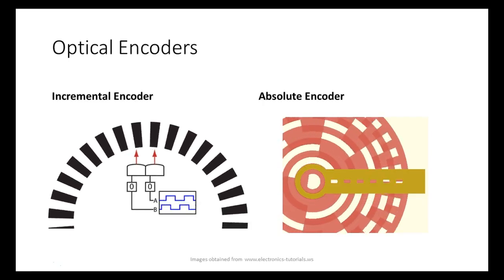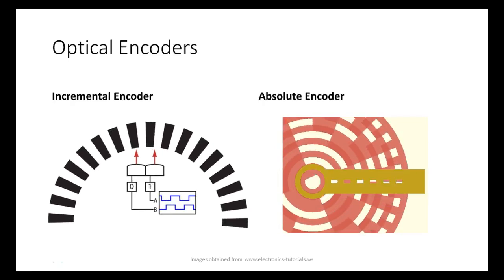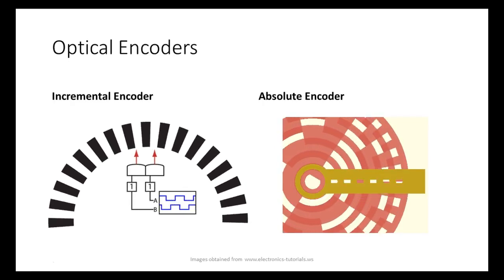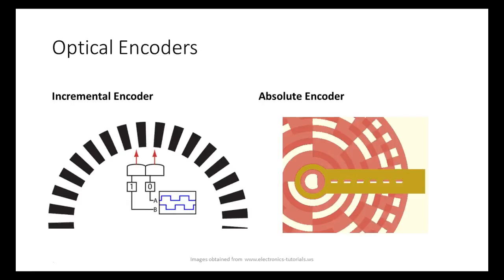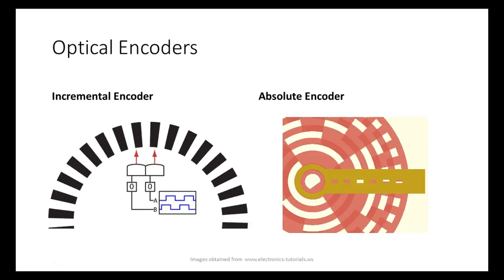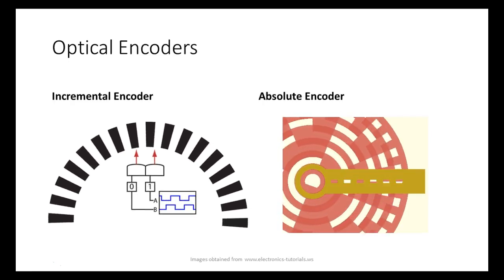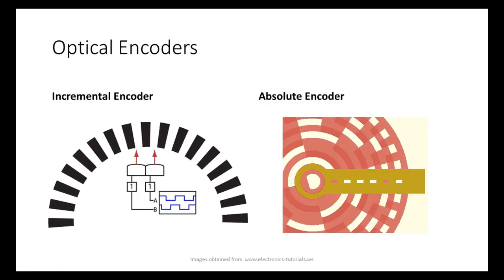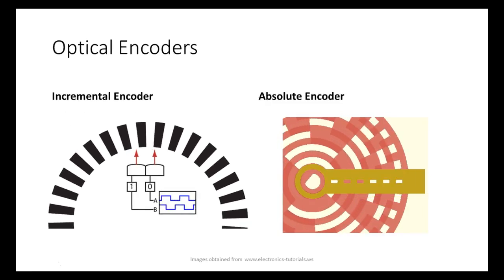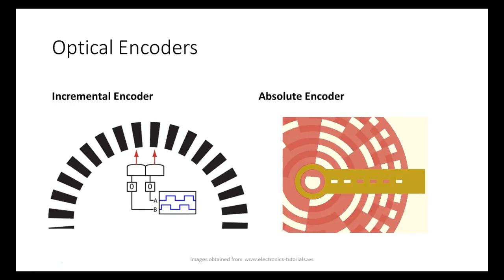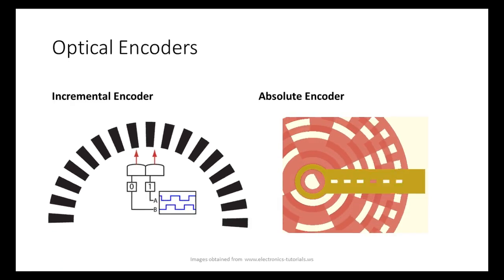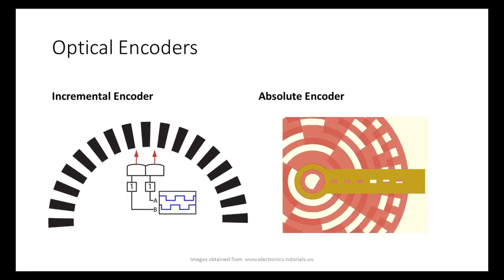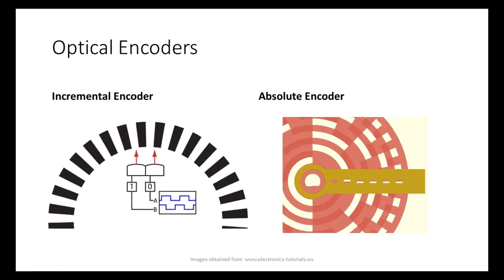What we do is we leave our robots on all the time. If the batteries go dead, we replace them. You only lose your origin if you lose power to the robot. Are we okay? So y'all know the difference between incremental encoders and absolute encoders. Just about all robots use incremental encoders. We lost the origin on that robot.